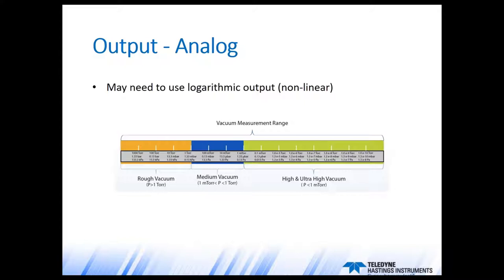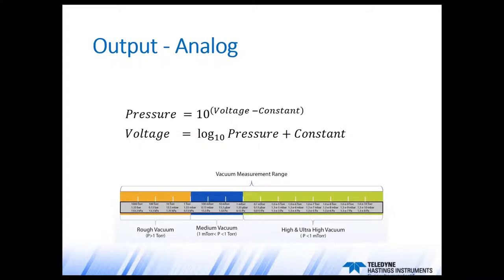For a vacuum gauge covering many orders of magnitude — say a combination gauge from atmosphere to 10⁻⁴ Torr, or atmosphere to 10⁻¹⁰ Torr — a single linear voltage output is not possible. If a full-scale value of 1,000 Torr corresponded to 10 volts, then 10⁻⁴ Torr would produce only 1 microvolt, which would be susceptible to noise. So some gauges provide a logarithmic output. You then take the voltage measurement, combine it with a constant from the manual, do the calculation, and easily convert from voltage to a pressure reading — you can even pop that right into Excel.